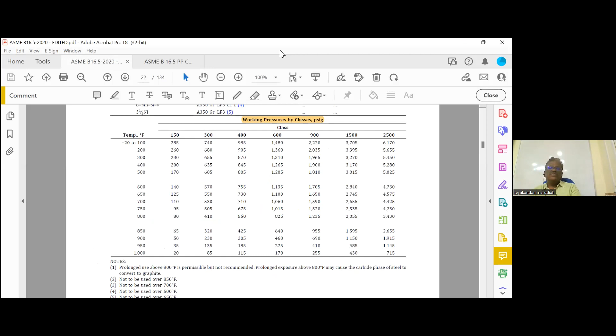So it can be averaged. If it is asking 450, between 400 and 500, you can average the pressure. It is allowed by the code. So for class 900 at 450, 1900 plus 1810 divided by 2. So what is the answer? 1855. So this is because of the averaging. 400 degrees Fahrenheit pressure and 500 pressure, divided by 2 you have to use.